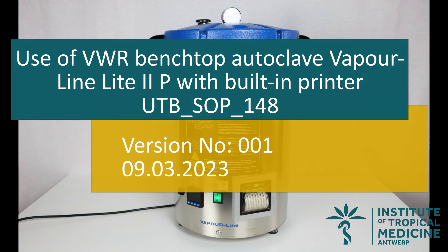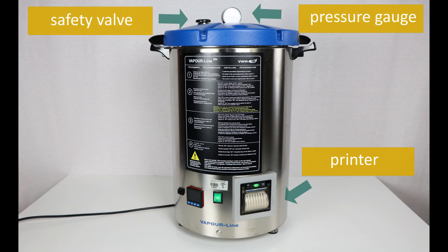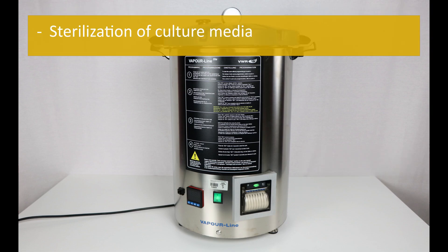Use of the VWR benchtop autoclave Vapour-Line Lite II P with built-in printer. Scope and application: the VWR benchtop autoclave Vapour-Line Lite II P is a semi-automatic steam sterilizer with a capacity of 23 liters and a built-in printer for sterilization of material at 121 degrees Celsius and a maximal pressure of 1.08 bar (15.37 psi). This procedure explains how to use the VWR Vapour-Line Lite II P benchtop autoclave for sterilization of culture media.